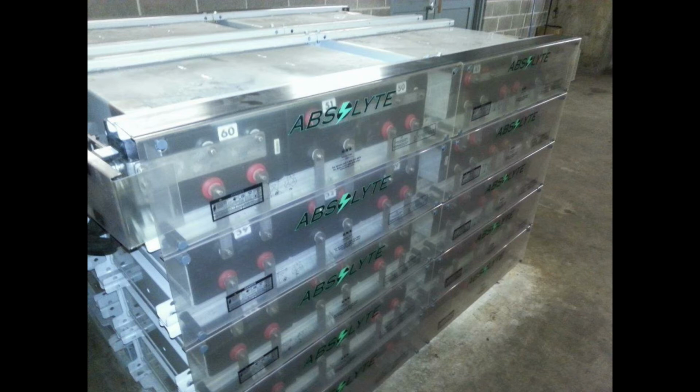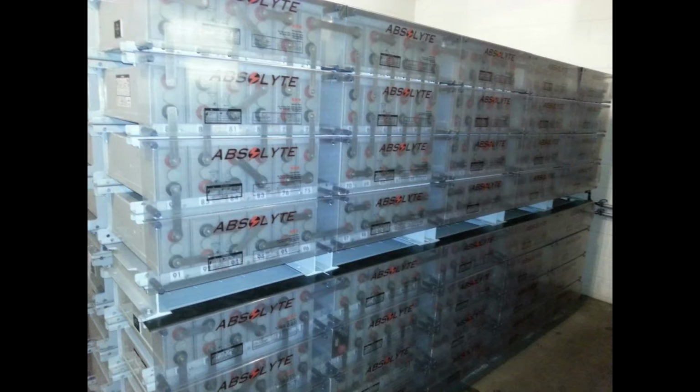First, you need to measure and record the most positive to ground and the most negative to ground. This is to give you an idea of approximately where to start measuring from individual cells to ground. Just divide the voltage of the lower number by the average volts per cell, and it gives you a starting point.